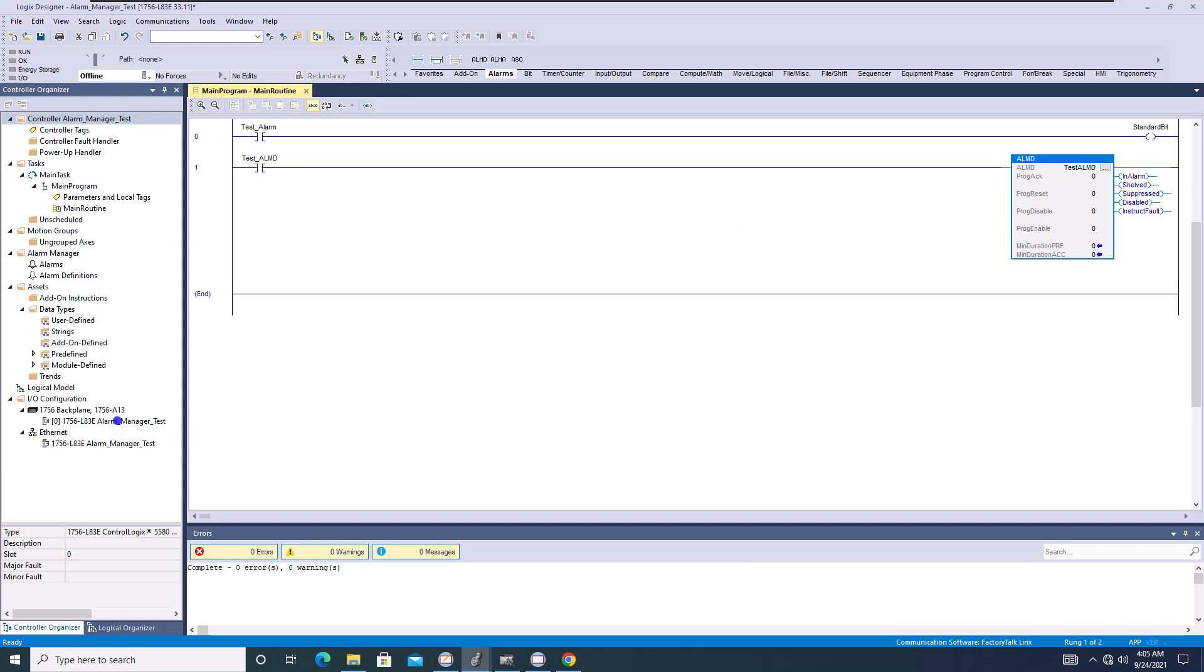Now the difference in the alarm manager and the ALMD, I will say is the ALMDs and ALMAs eat up a lot of memory inside of your processor. Now with the L8 processor, you are probably not worried about the memory so much unless you have a really huge program. But again, when it comes down to it, they do eat up a lot of memory and they are memory intensive. But when it comes to having a machine that is very detailed and gives you the alarm at the proper, precise timing that you need, then an ALMD is preferred in my opinion.